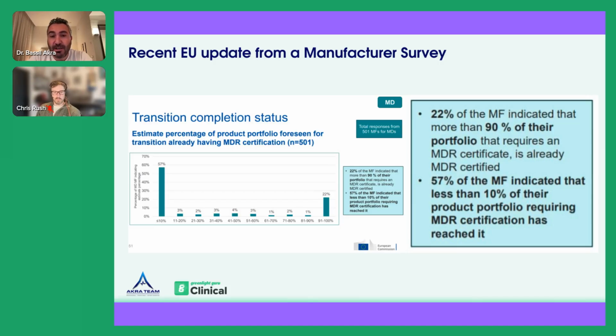What is actually shocking for everyone is that today we have additional time to place devices on the market till 2027, 2028, depending on the risk class of the device, which was provided by the European legislator as a measure after a detailed survey in 2022, where they recognized that we are heading toward the deadline of May 2024, and already in 2022 only 10% of the MDD certificates had been issued under the MDR.